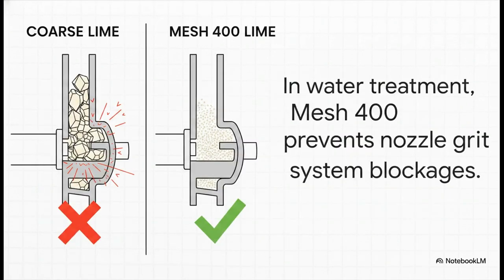And when it comes to water treatment, one core rule governs everything: fineness. Calcium hydroxide has incredibly low retrograde solubility. That actually means it dissolves less as the water gets warmer, which is pretty wild. So dosing it into a system is essentially just dispersing a solid suspension.